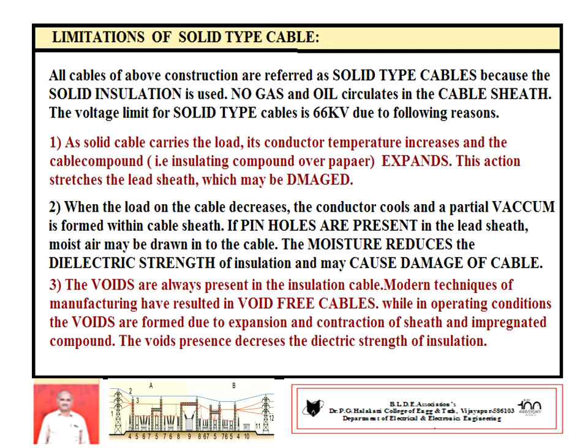Next, we have to discuss the limitations of solid type cables. So up to this point, what we have discussed, the different types of cables, all belong to the solid type of cable because the dielectric used is purely solid. There is no combination of oil, there is no combination of gas. Hence, these are referred to as solid type cables. But the use of solid type cables is limited to 66 kV with much better dielectric strength.